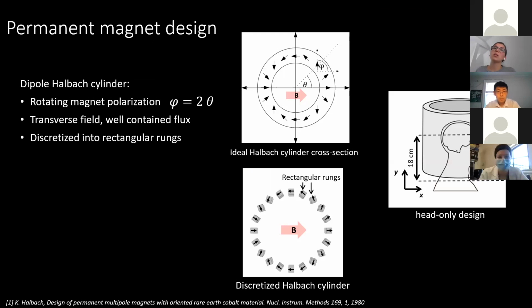The first component, which I mentioned is the most important, is the permanent magnet that creates the B0 field, or the main polarizing field. For this design, we used a dipole Halbach cylinder design. In an ideal Halbach cylinder, we have a rotating magnet polarization along the cylinder, and it creates a transverse B field in the center, with a very well-contained flux. The fact that the flux is really well contained in the magnet is really advantageous for a portable system, because it means you don't have to worry very much about stray fields. Basically, just a few centimeters away from the magnet, the field is very low, so you don't have to worry about other instrumentation in the room being attracted to the magnet.